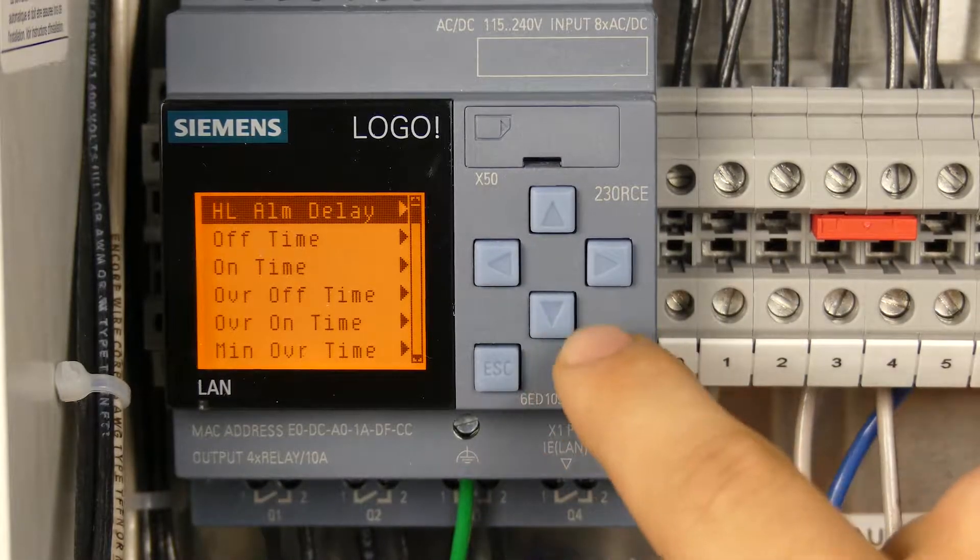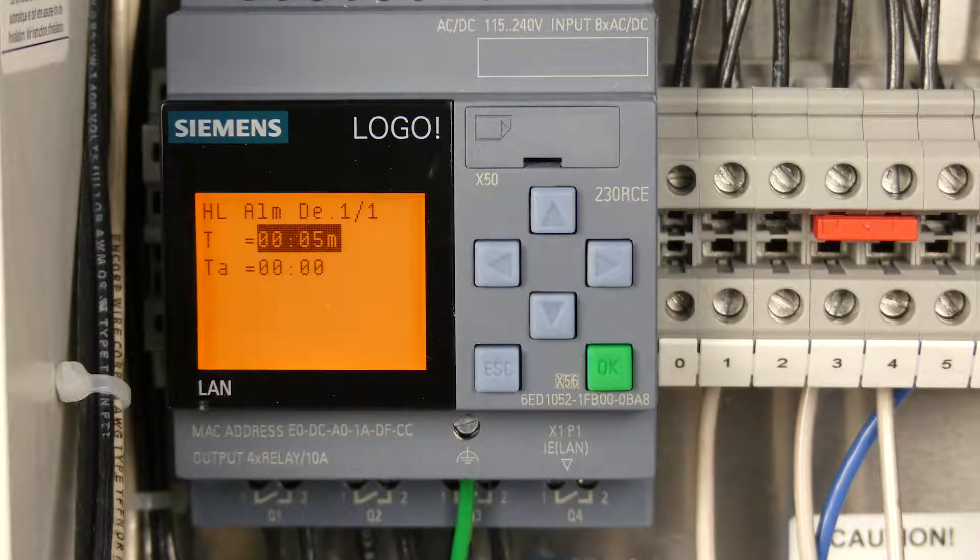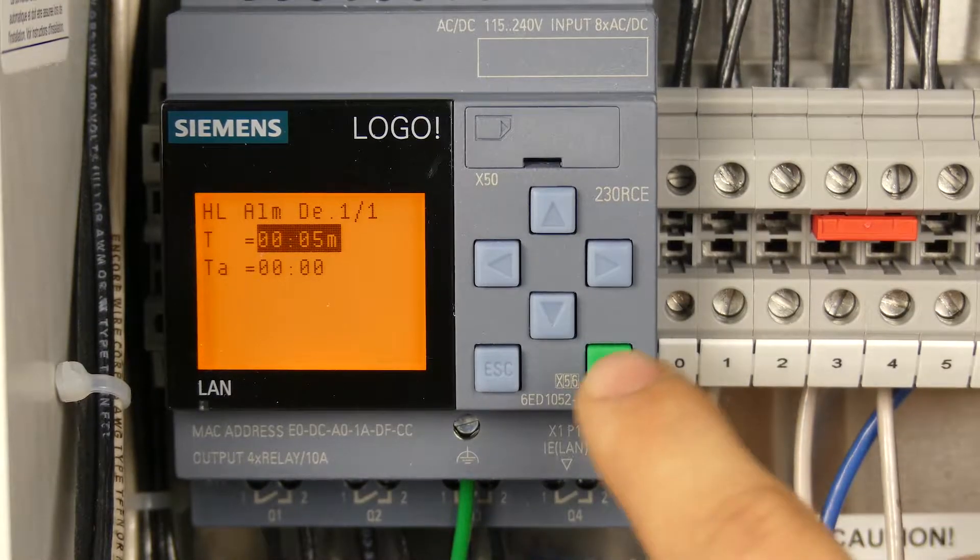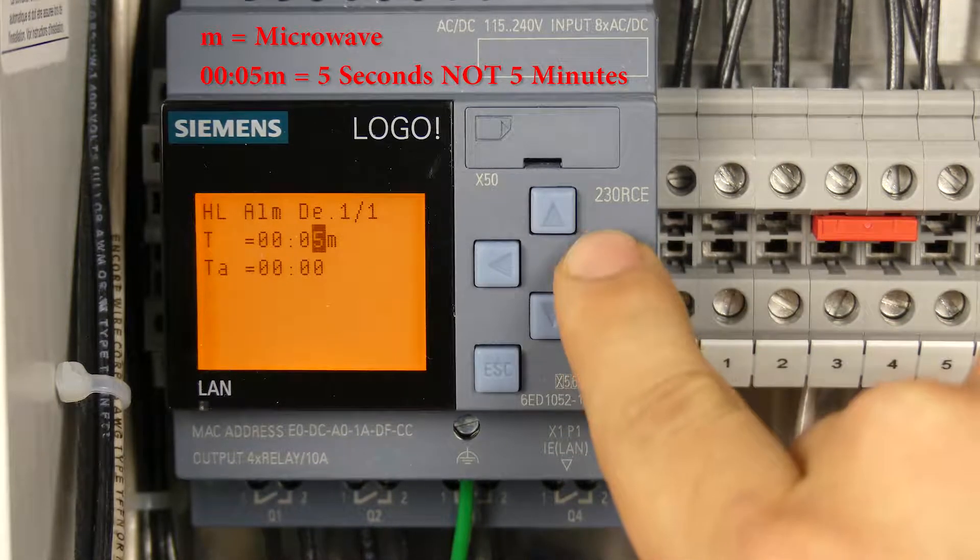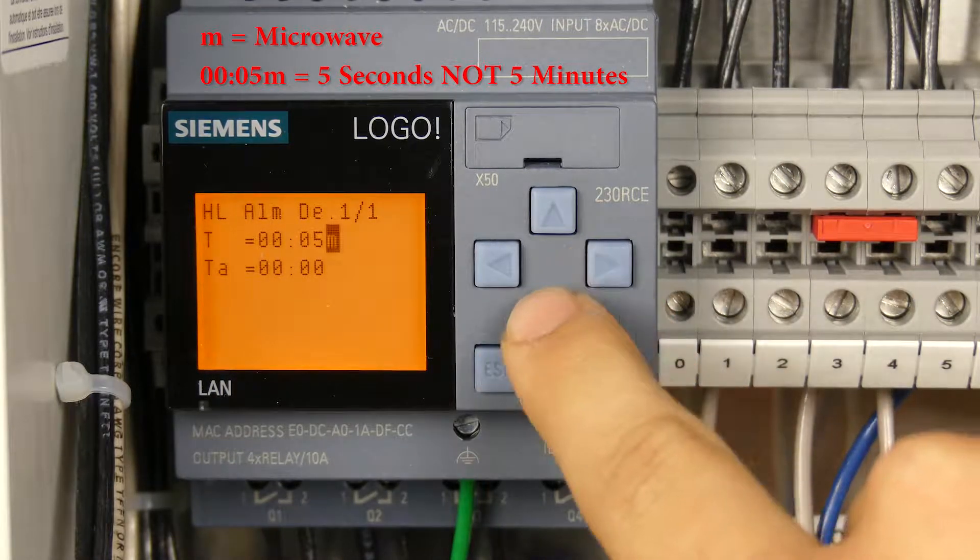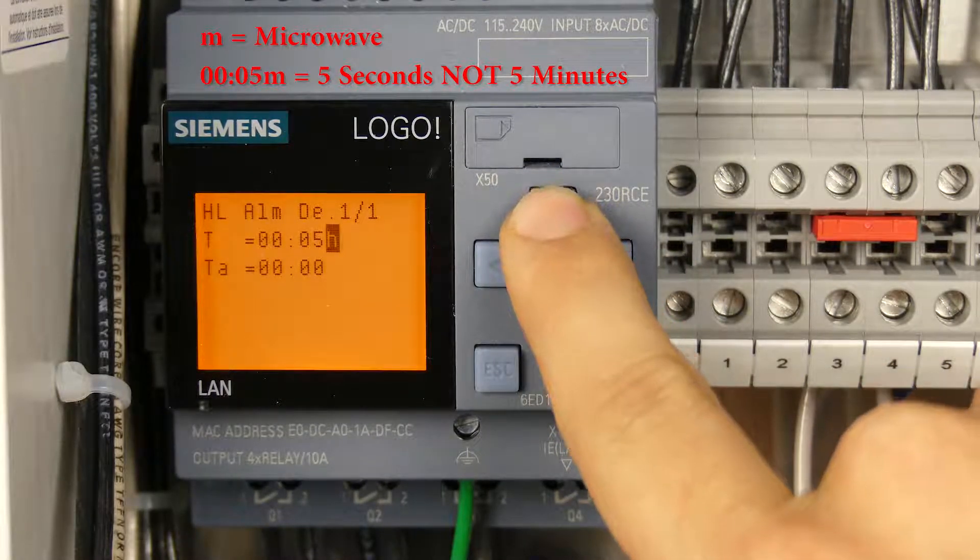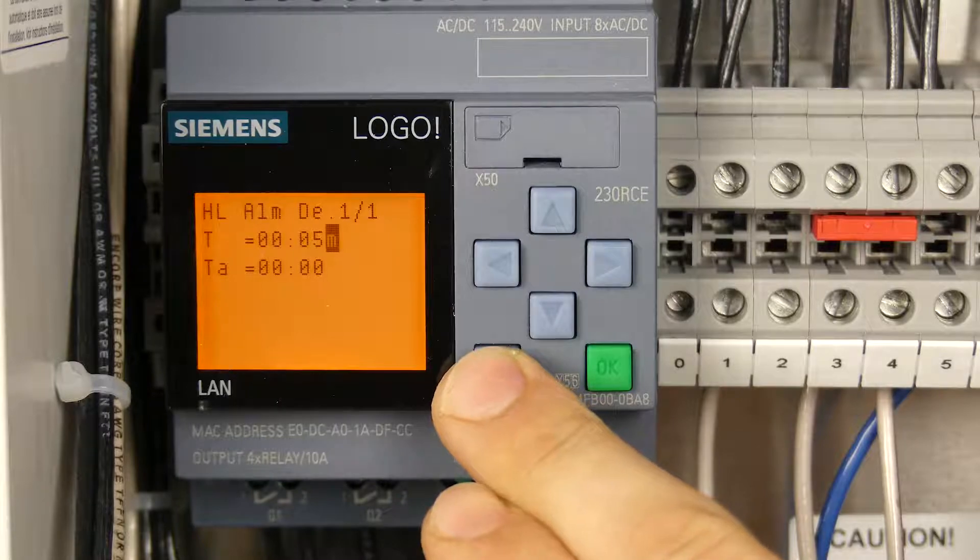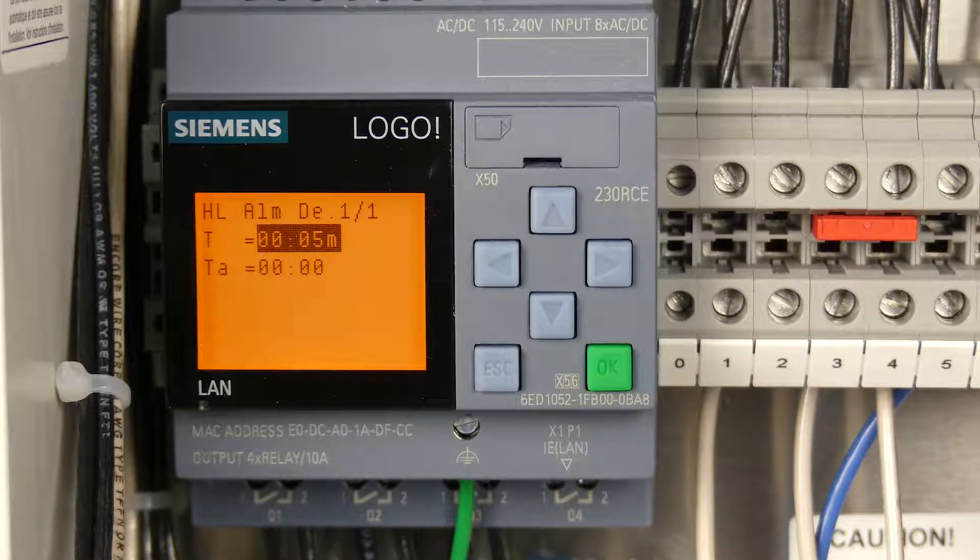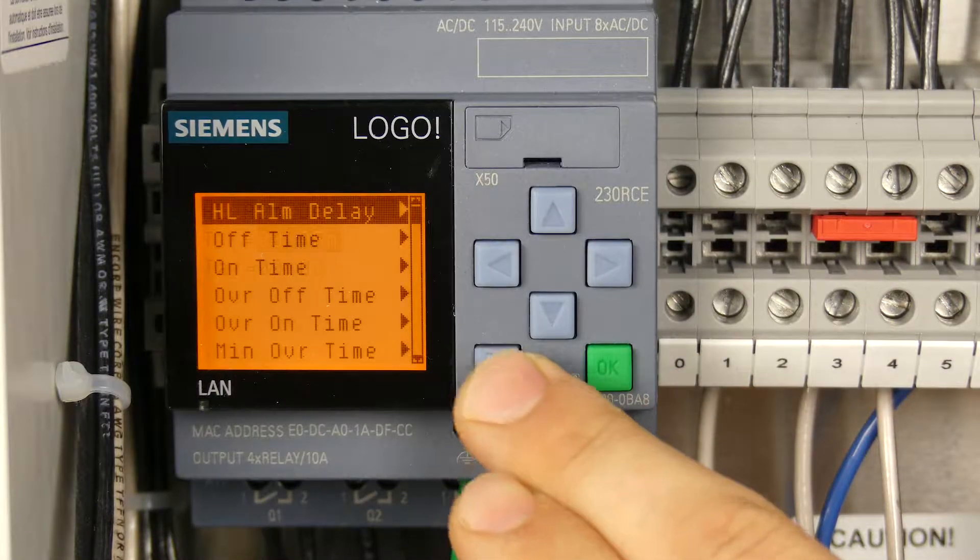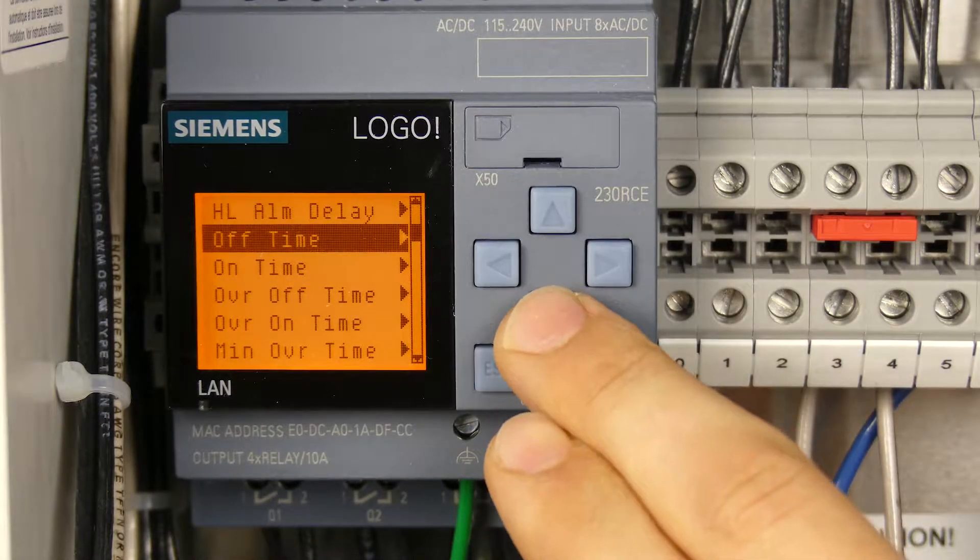The very first one we'll talk about is the high level alarm delay. The high level alarm delay is going to allow you to delay the amount of time between the alarm float becoming activated and the alarm actually sounding. The default is set to five minutes. You simply press OK to enter edit mode and you can travel left and right to adjust any one of these up or down. You can also change it from minutes to seconds to hours. This is a very useful feature to avoid nuisance alarms where a timed dose system can be allowed a little bit of time to catch up. It's more common to have the alarm delay extended to allow the system to catch up when it enters override mode.